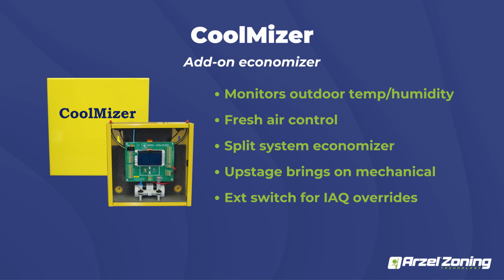It's also going to have an external override switch that's built onto the panel, which can be used for a number of different uses, but one of the most popular is just using for carbon monoxide detection. Say you could set it up to a carbon monoxide detector with dry contacts. If your carbon monoxide alarm gets too high in that building, it would close those contacts and force the dampers open to bring in that fresh air and mix that air so you're not hitting those limits as far as carbon monoxide and that kind of stuff.